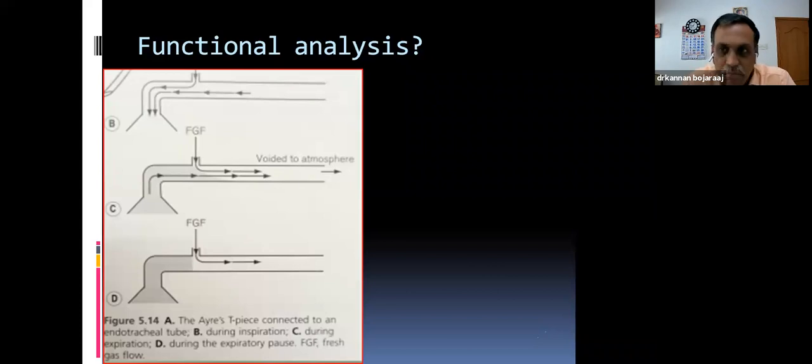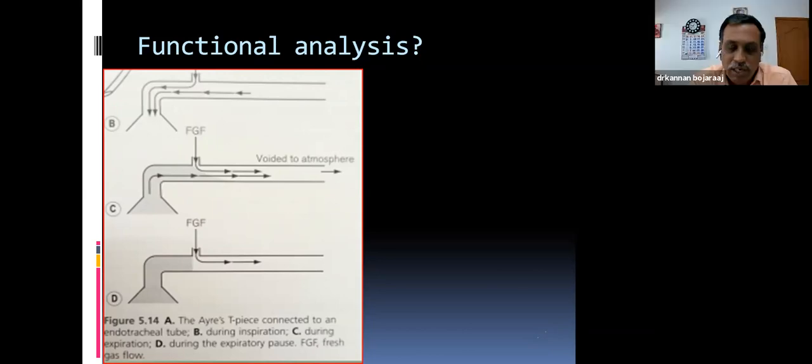It is the most satisfactory arrangement in Mapleson E and F systems. However, if the capacity of the reservoir is reduced, the flow rate must be increased enormously. Otherwise, air dilution will occur.